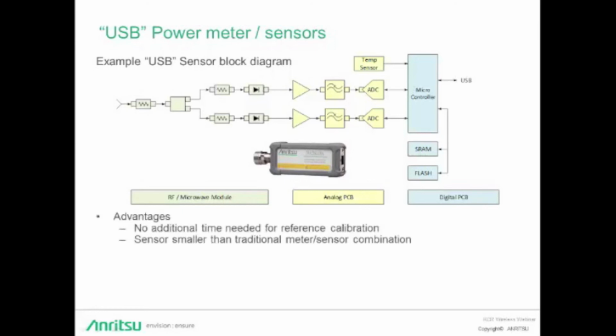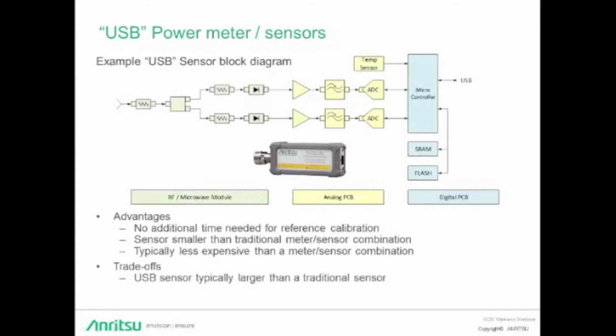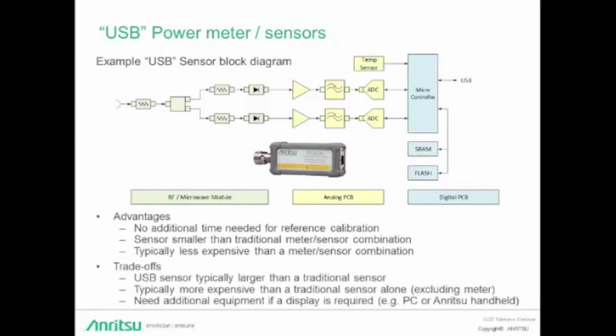Some of the advantages: you have no additional time needed for reference calibrations. The sensor itself is smaller than a meter and sensor combination and is typically less expensive than a meter and sensor. The trade-off is that a USB sensor is typically larger than just a traditional sensor and typically more expensive than a traditional sensor alone, excluding the meter. And then finally, if you need a display, additional equipment is required, like a PC or an Anritsu handheld.